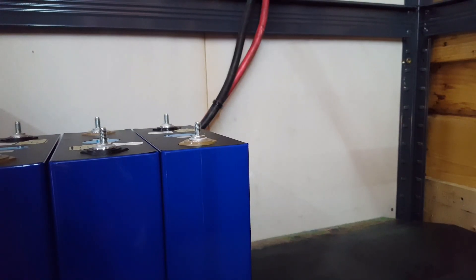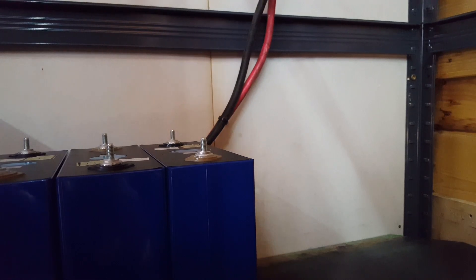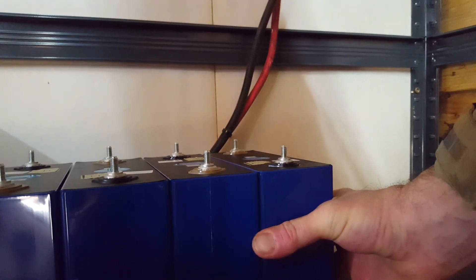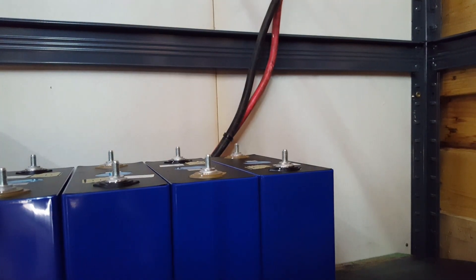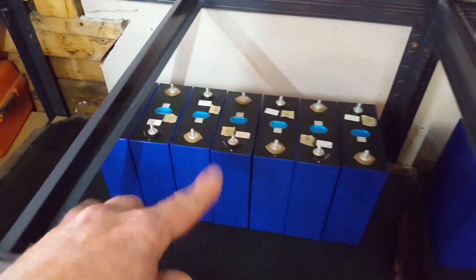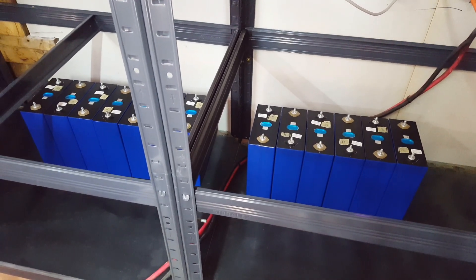Numbers 13, 14, 15 and 16. Number 13 is a low cell, 14 is a low cell, and 15 and 16 are high cells — cool. I can't be filming all this, I need both pairs of hands. Just give them a quick dust off, wipe of the terminals — positive, negative, positive, negative. Lovely. No horrendous bloaters yet; there's a couple that are slightly bulging, but it's not a big bad bloater, so should be okay.